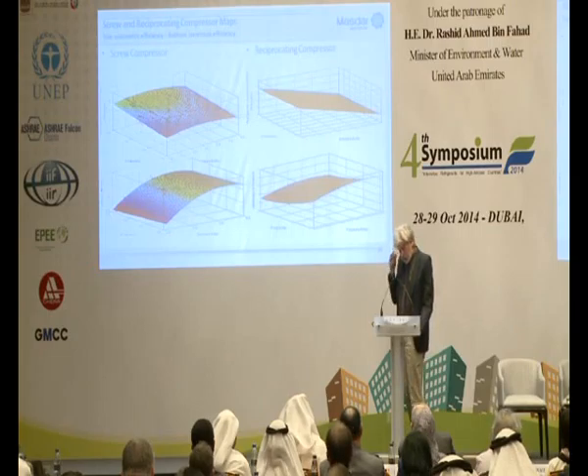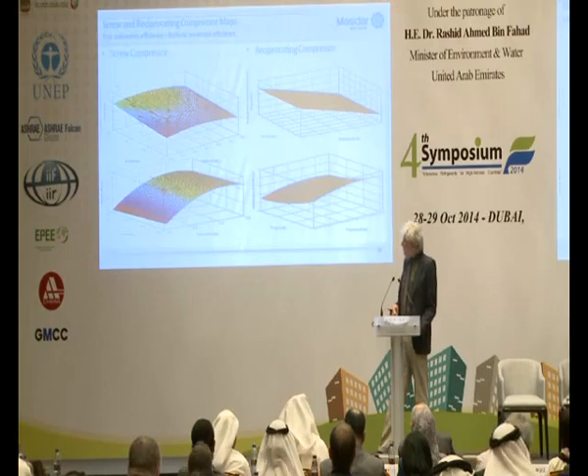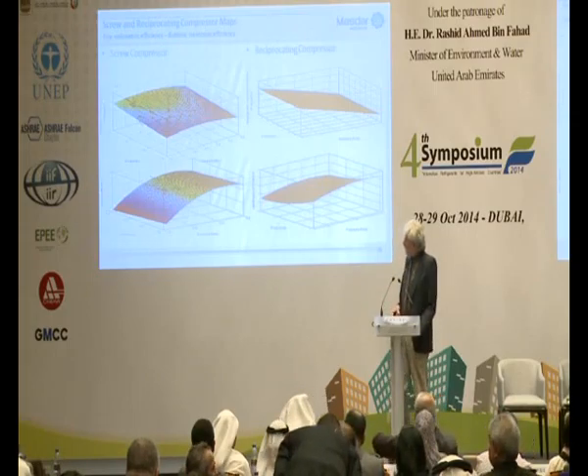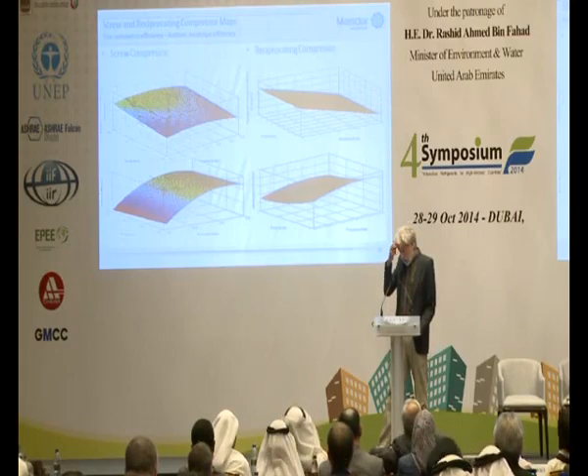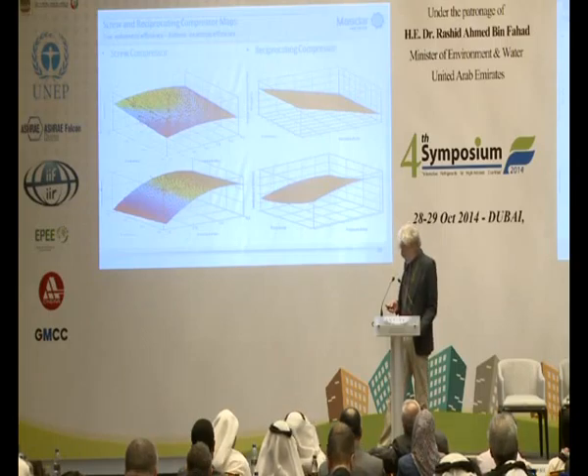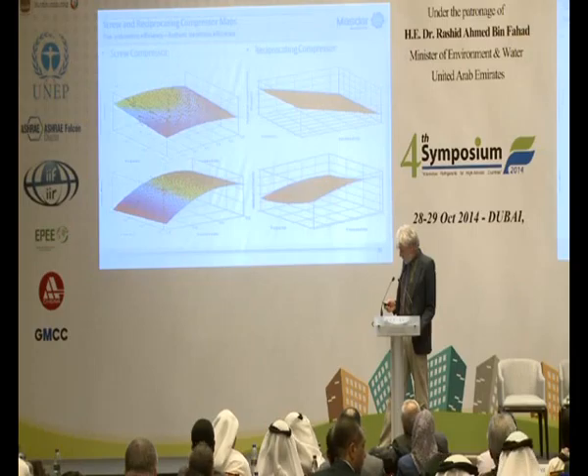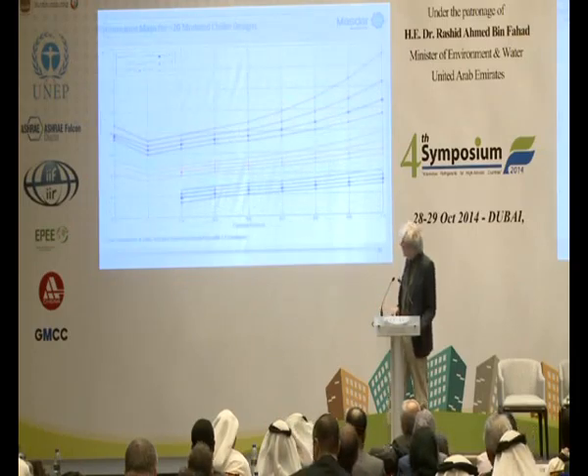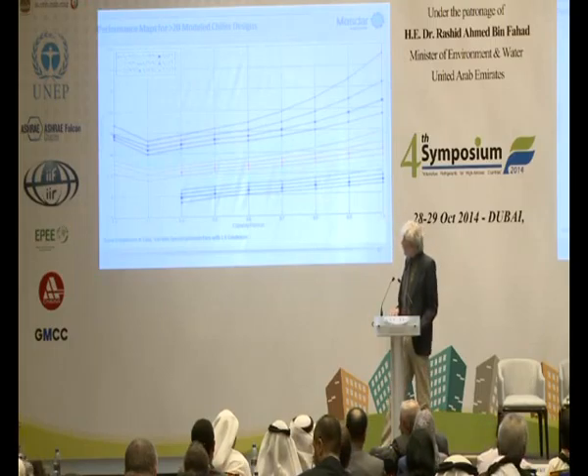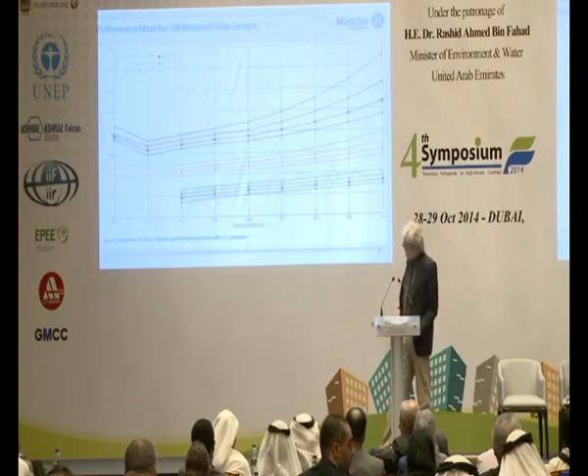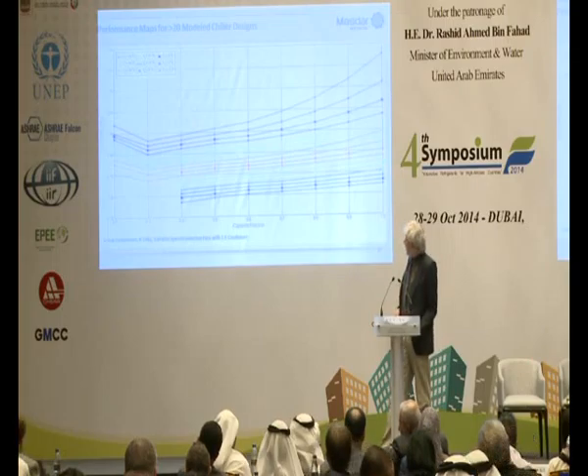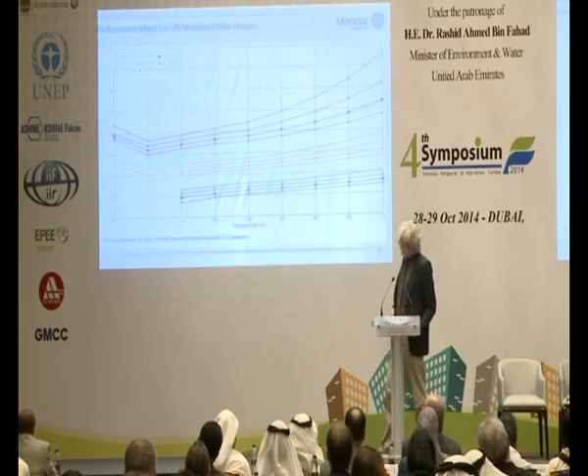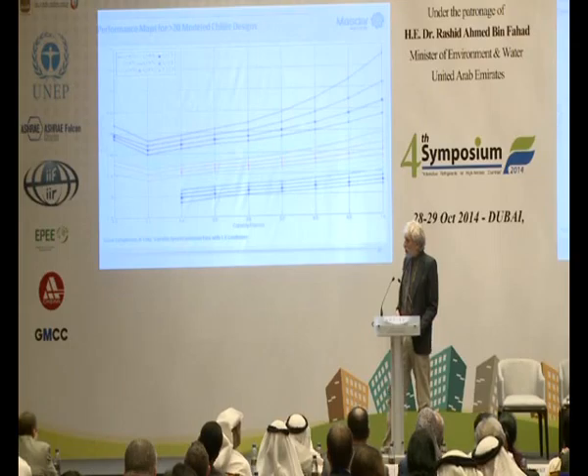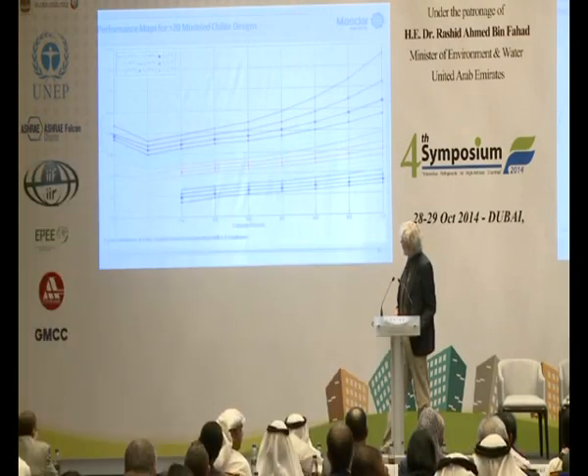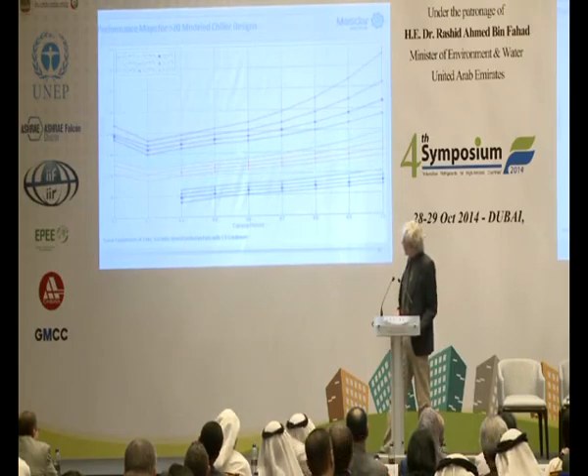Now, from this collection of components, condenser, evaporator, throttling device, and compressor, and of course the refrigerant properties have to be evaluated, at any given condition we can determine the chiller COP, or I'm going to speak in terms of specific power, so 1 over COP. And what we end up doing is running the model at a wide range of conditions. Here we have capacity fraction in tenths from 0.2 to 1, outdoor ambient, and you'll have to forgive me, we went as high as 45 C, and I think we'll go back and raise it a little higher. And I'll return to that in a moment. And then evaporating temperatures from -1 to 5 C.